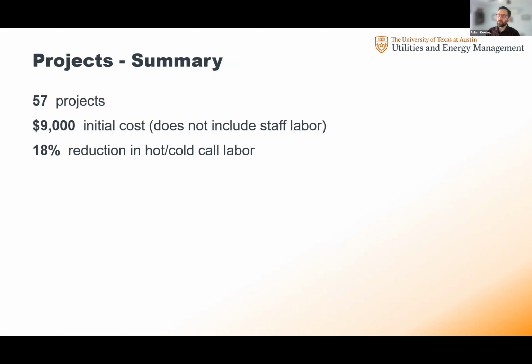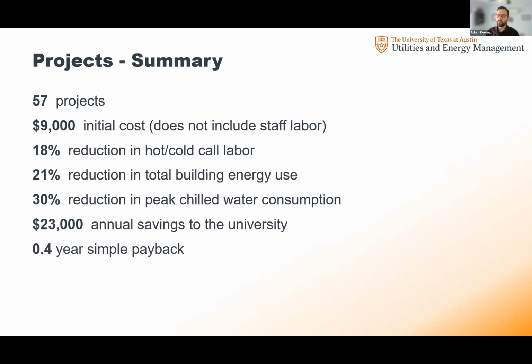Here's a quick summary of some projects we've done over the years. We're averaging about $9,000 in cost, not including staff labor. We've reduced hot-cold calls for maintenance by 18%, about 20% energy reduction per project, 30% peak chilled water reduction, and saving about $23,000 a year per project. So that's a 0.4-year simple payback.